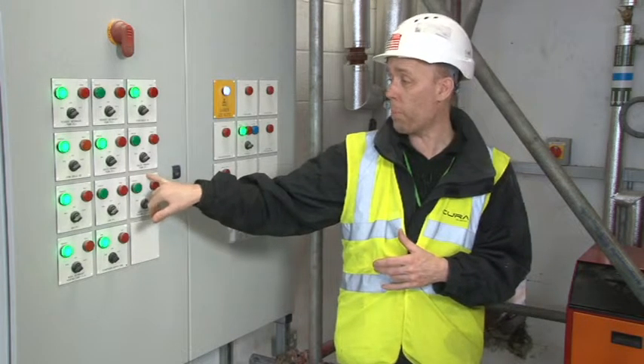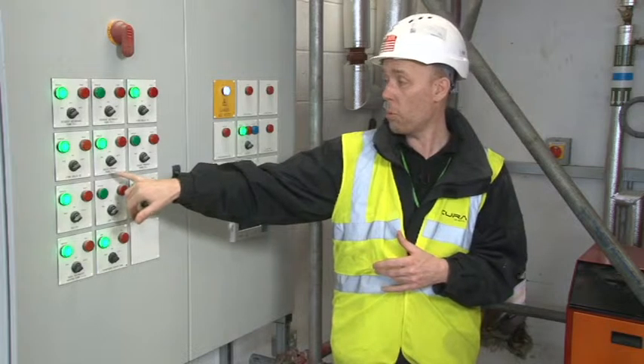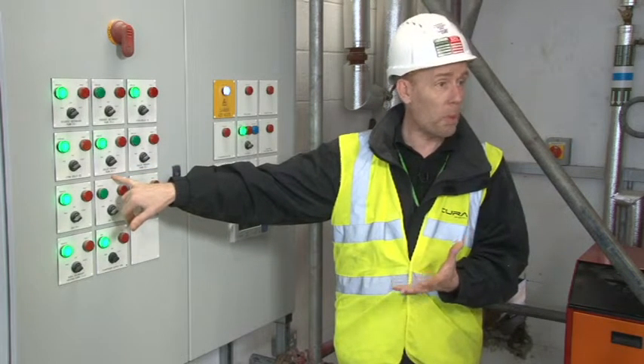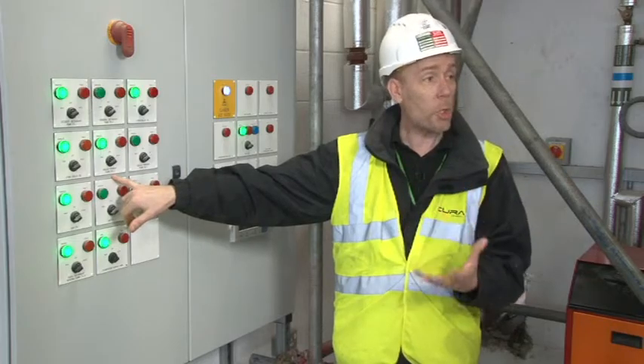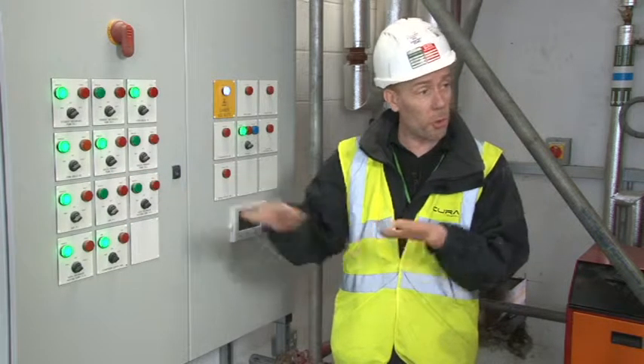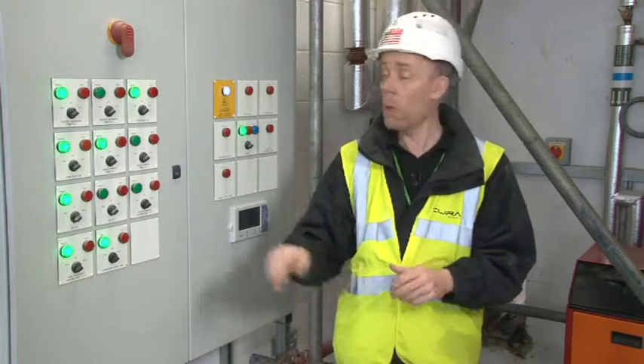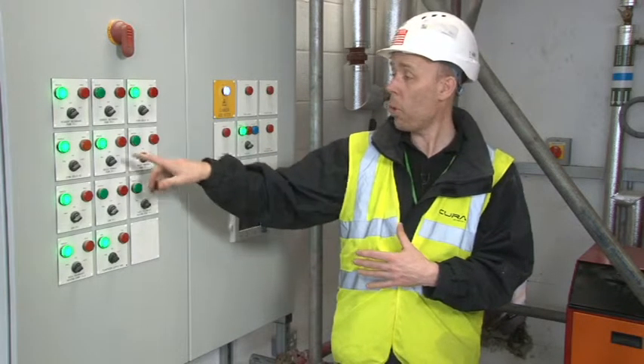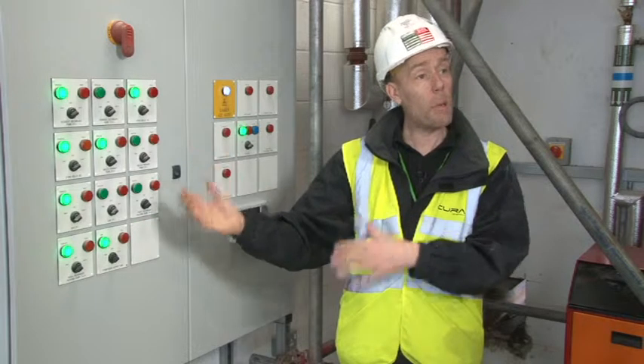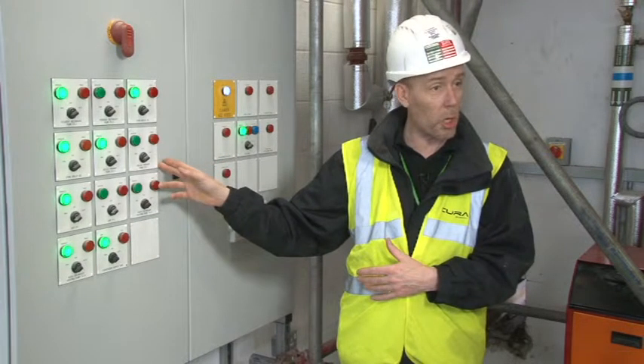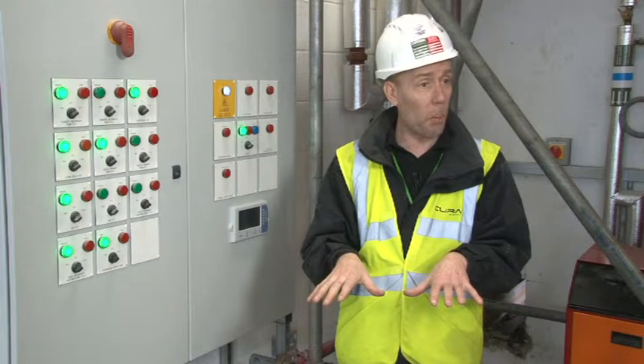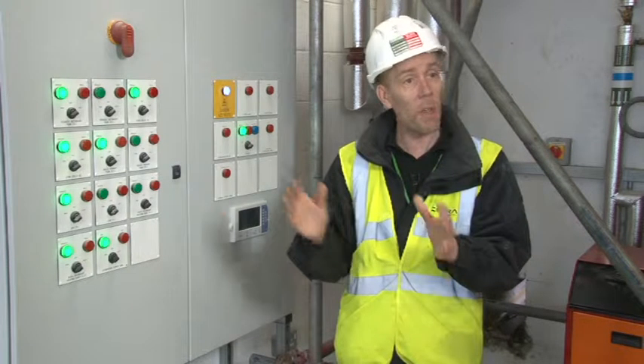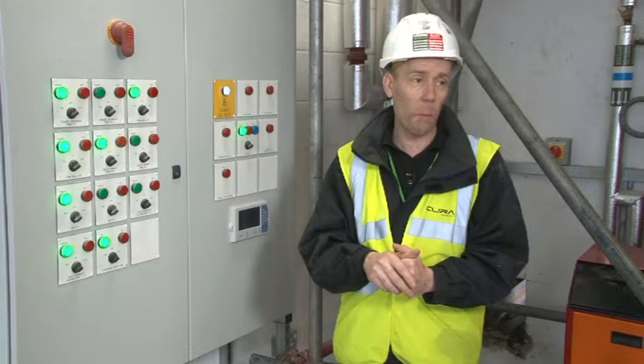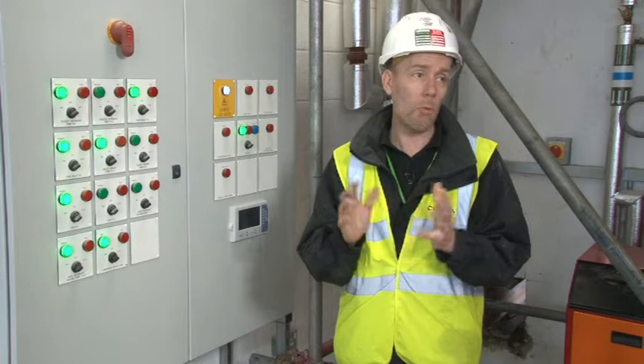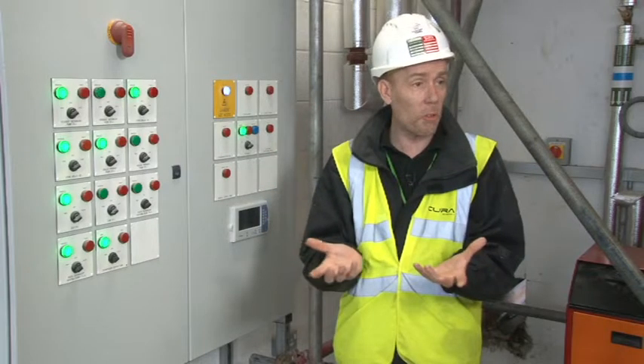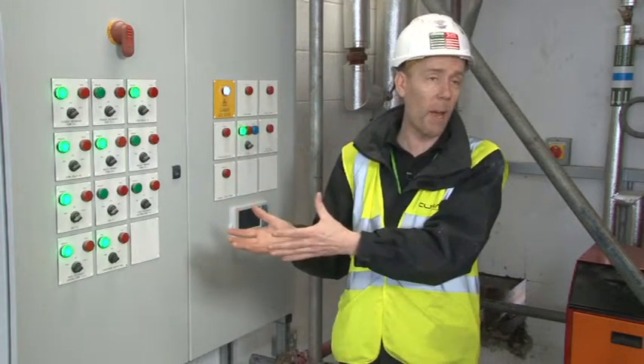So where we have 2 pumps, we have 2-1 and 2-2. Normally 2-1 would be the pump that would be running for this week. Each week it will change over to the other pump, so we get even wear and tear on the equipment. So if you came in on, say, week 1, all of the 2-1s should be running. If you came in on week 2, all of the 2-2s would be running, unless there was any fault with any of the pumps or any of the flow switches, in which case it will default back to whichever pump was working. So that way you never get a building where there is no heat being circulated, because we have 2 pumps, there's always a backup.